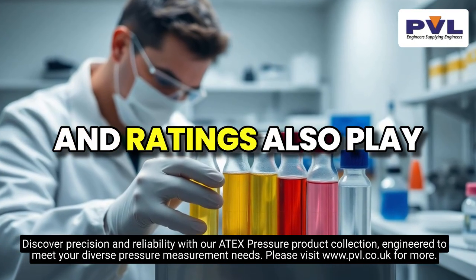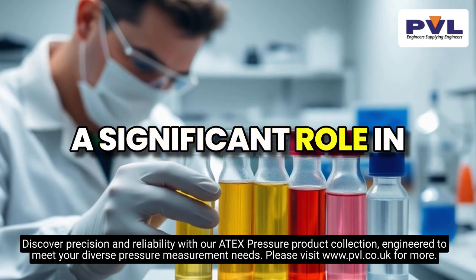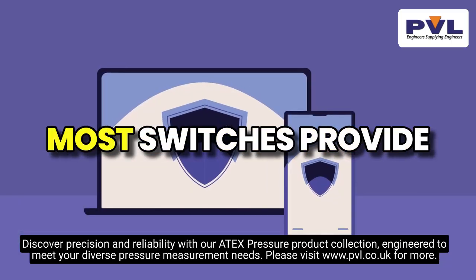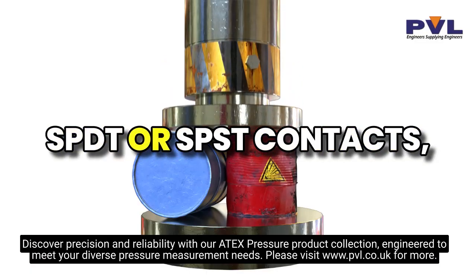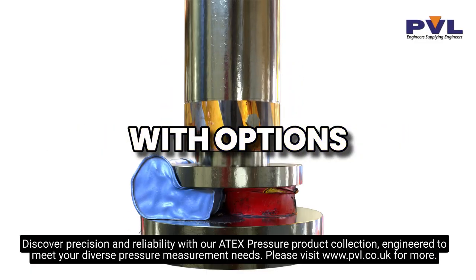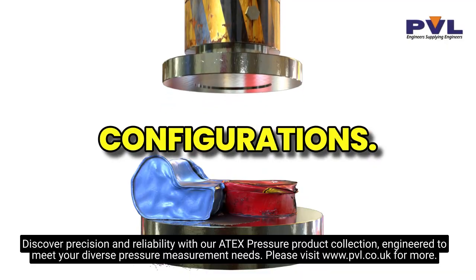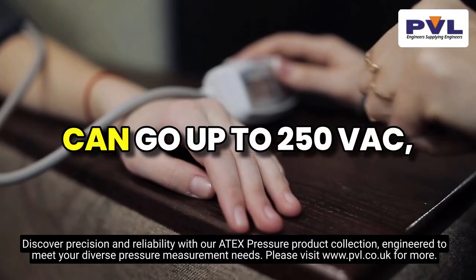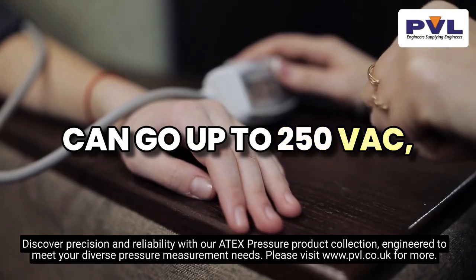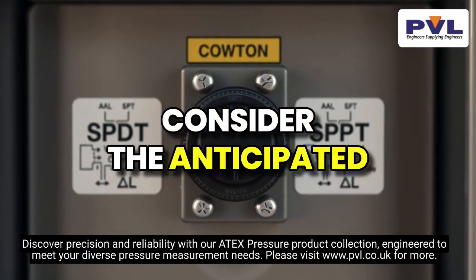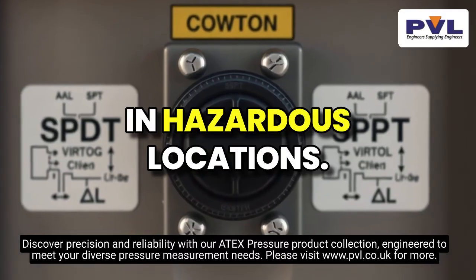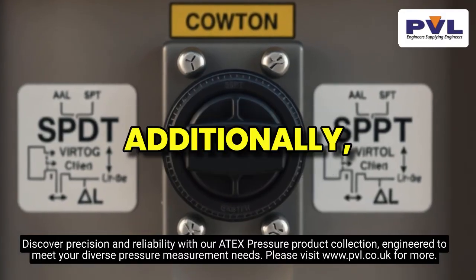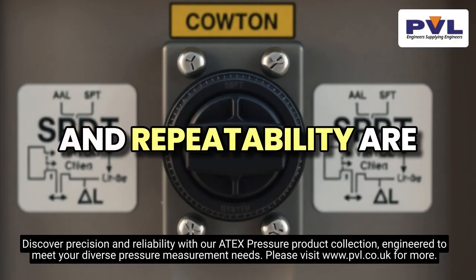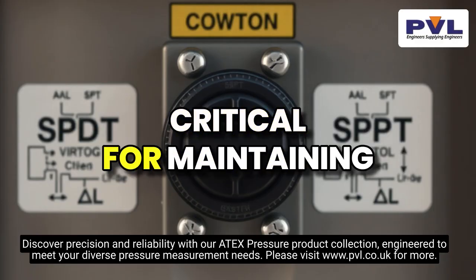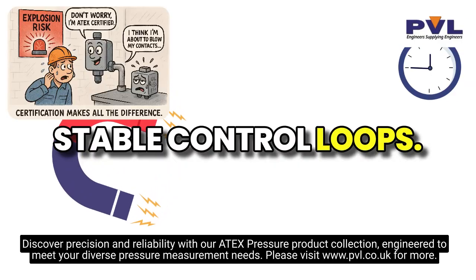Electrical contacts and ratings also play a significant role in the selection process. Most switches provide SPDT or SPST contacts, with options for normally open or normally closed configurations. The switching voltage can go up to 250 VAC, but it's crucial to consider the anticipated load and derating in hazardous locations. Additionally, the actuation hysteresis and repeatability are critical for maintaining stable control loops.